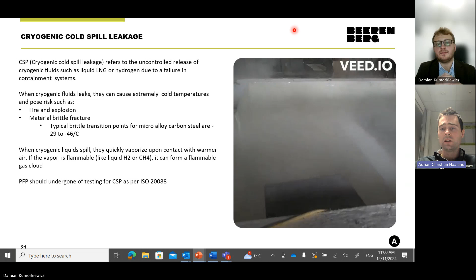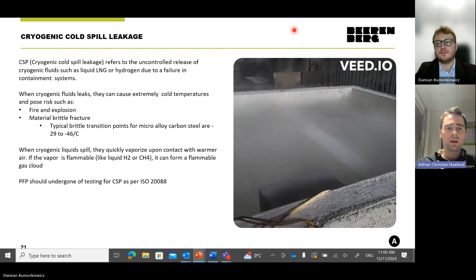After the test, it's taken directly from the cryogenic test setup and erected into the jet fire chamber and subjected to jet fire temperature exposure at 1200 degrees Celsius. Not all systems can withstand this. We have tried different technologies, different products in the past. Some products crack and delaminate due to the extreme temperature shock. Some explode because liquid gas is trapped behind the PFP, and others fail integrity-wise in the fire. These types of tests are key to ensure that our products live up to their intended purpose when used in, for example, LNG applications.